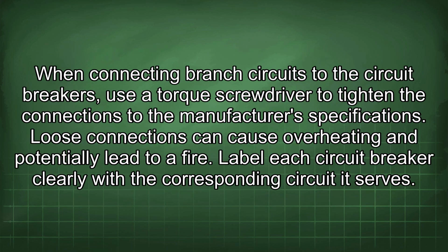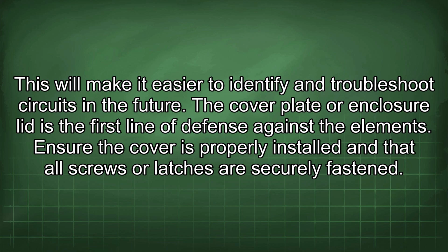When connecting branch circuits to the circuit breakers, use a torque screwdriver to tighten the connections to the manufacturer's specifications. Loose connections can cause overheating and potentially lead to a fire. Label each circuit breaker clearly with the corresponding circuit it serves. This will make it easier to identify and troubleshoot circuits in the future.